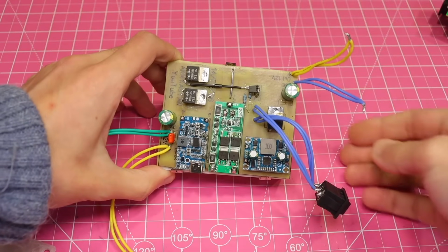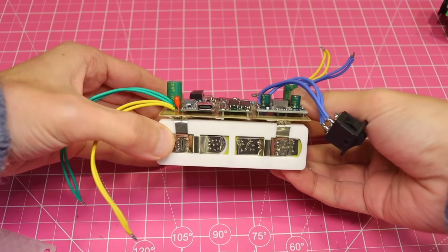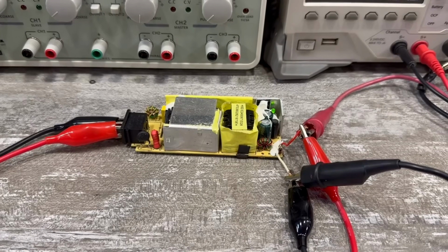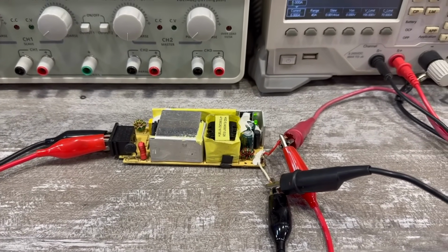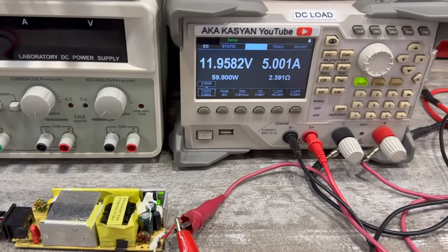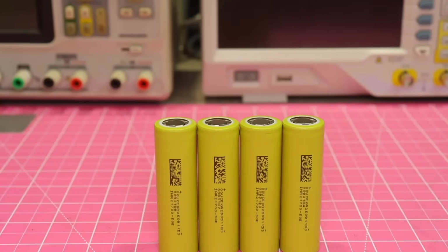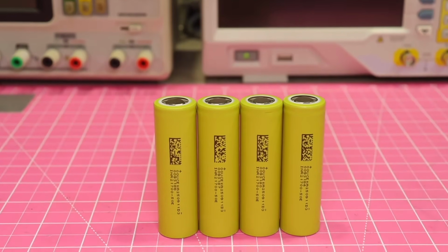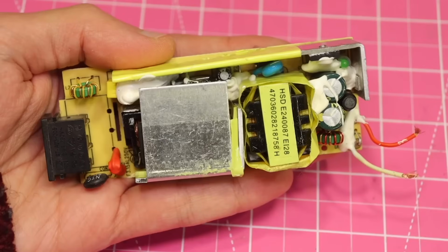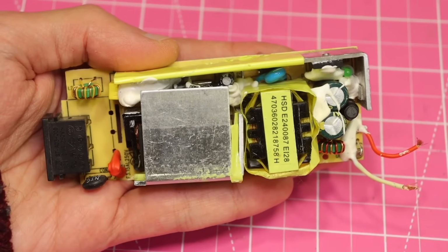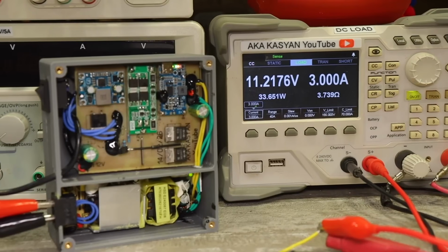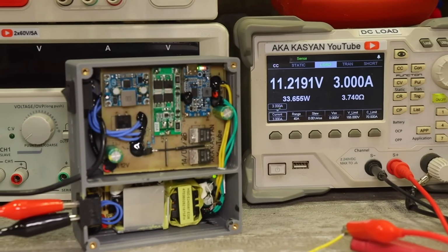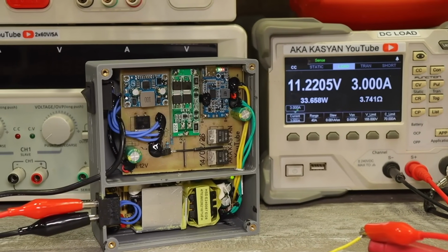When the UPS battery is fully charged, the power supply feeds the load directly and can deliver almost all of its usable power to it. But there could be a situation where the battery is completely drained and the load is powered at the same time. In that case, the power supply has to both charge the battery and power the load simultaneously. That's why you need some power reserve, enough to charge the battery.